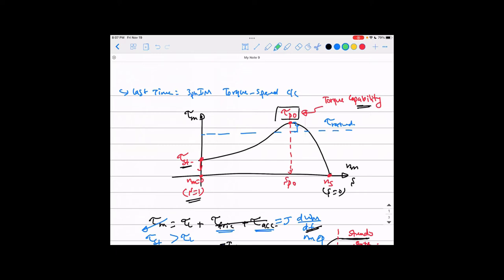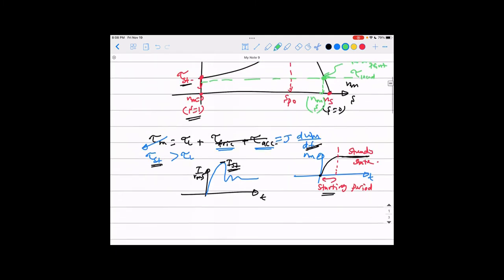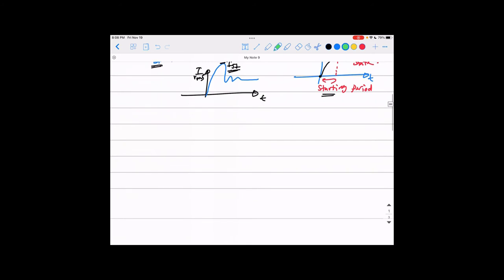The actual torque the machine produces depends on the load. If you plot the load torque as a horizontal line, the intersection between the load torque line and the motor's torque-speed curve is called the operating point. From that point you can read the actual speed and slip at which the motor is working. This curve represents the capability of the machine — it doesn't mean you're producing pullout torque all the time; the motor just responds to the load.